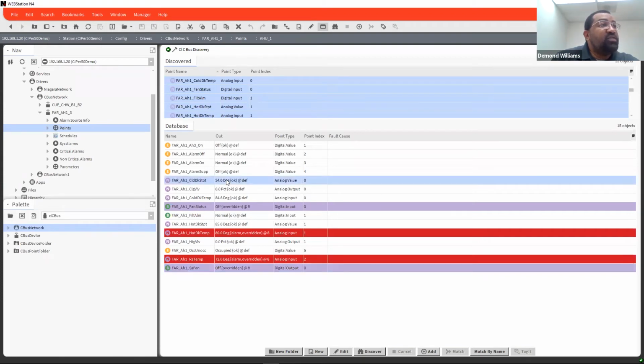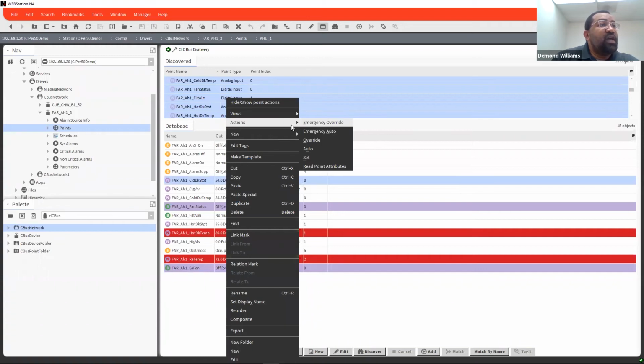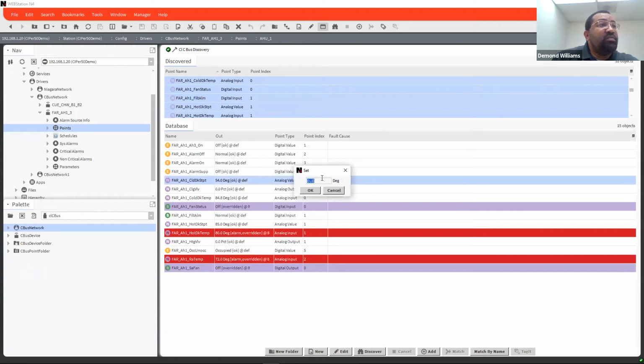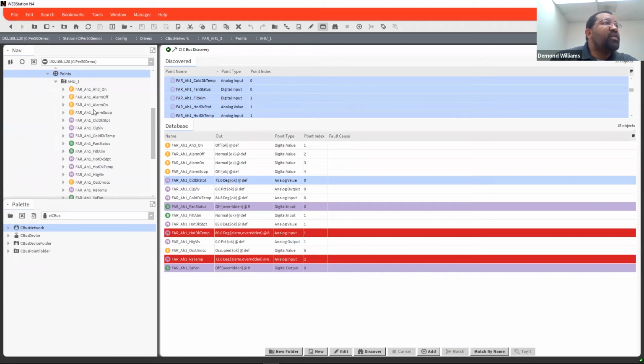So if I need to change any set points, anything, I can do it as simple as going to set or override, and then basically just changing it just like I do any other Niagara system. So like I say, once you bring it in, it acts no different than any other LON system, BACnet system, or anything like that.